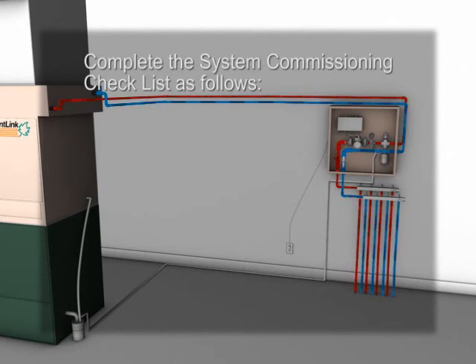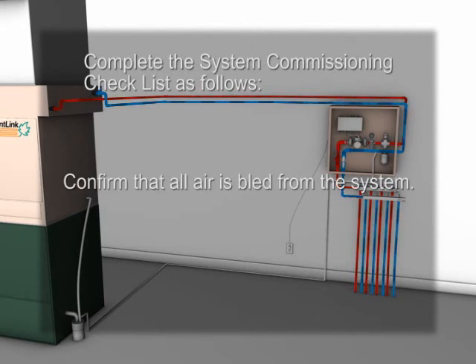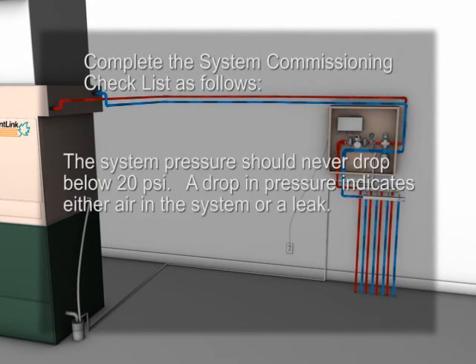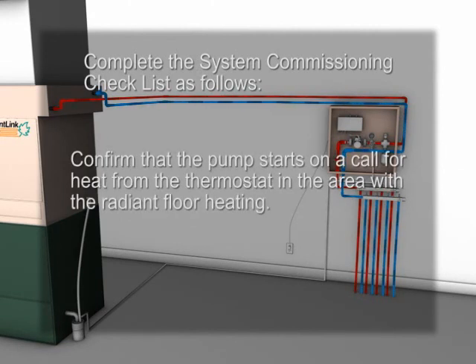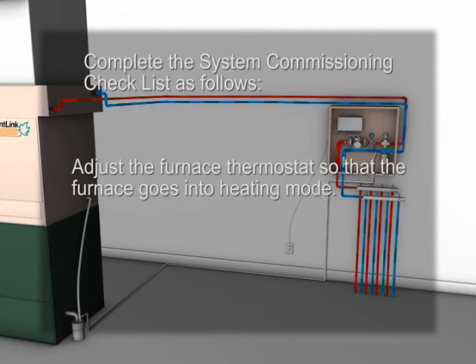Complete the system commissioning checklist as follows. Check for leaks. Confirm that all air is bled from the system. The system pressure should never drop below 20 psi. A drop in pressure indicates either air in the system or a leak. Confirm that the pump starts on a call for heat from the thermostat in the area with the radiant floor heating. Adjust the furnace thermostat so that the furnace goes into heating mode.